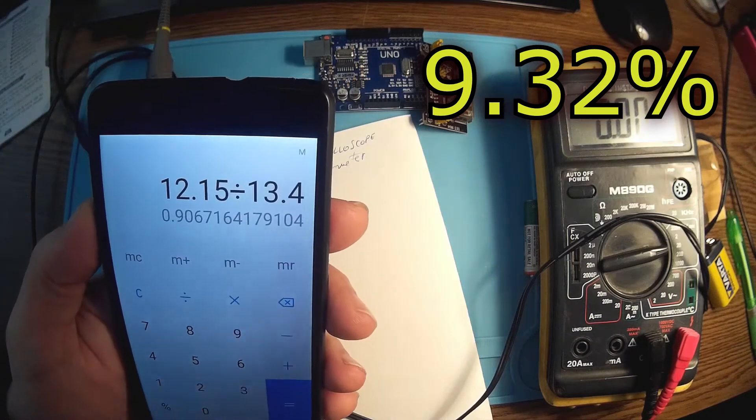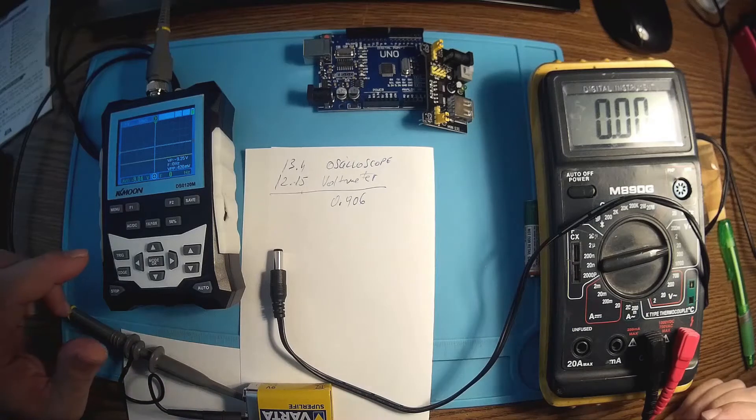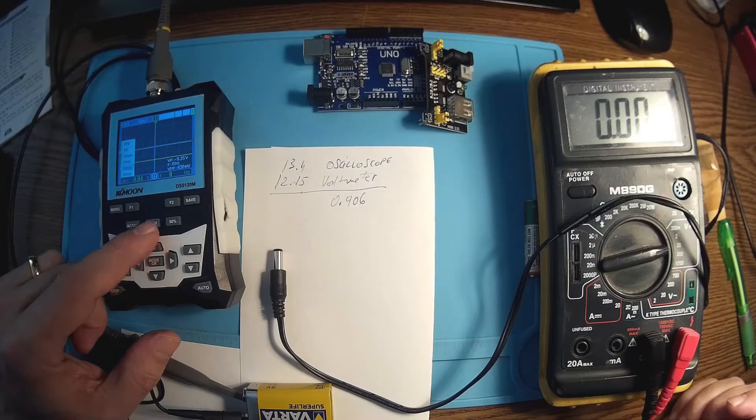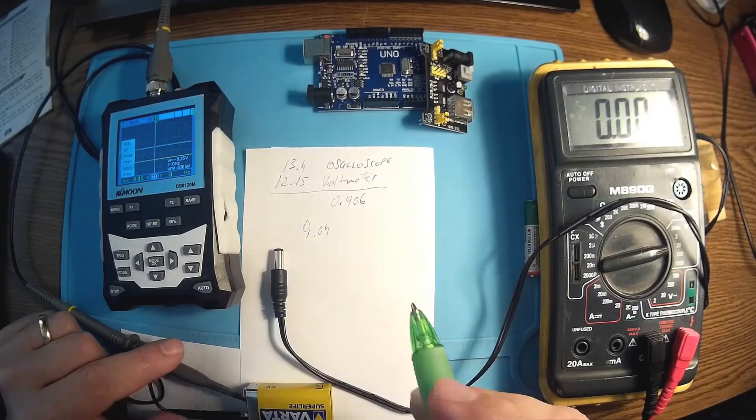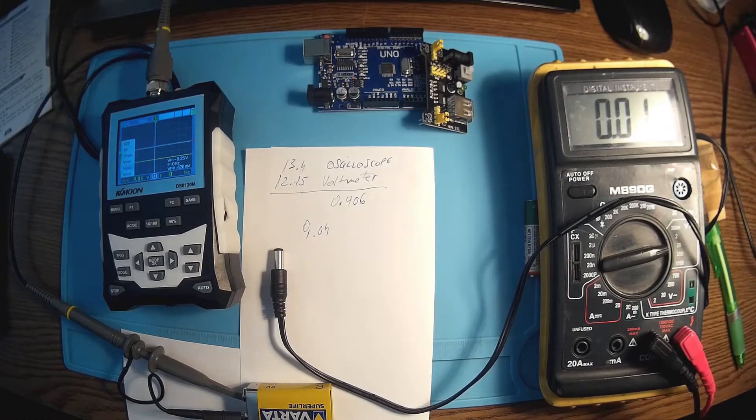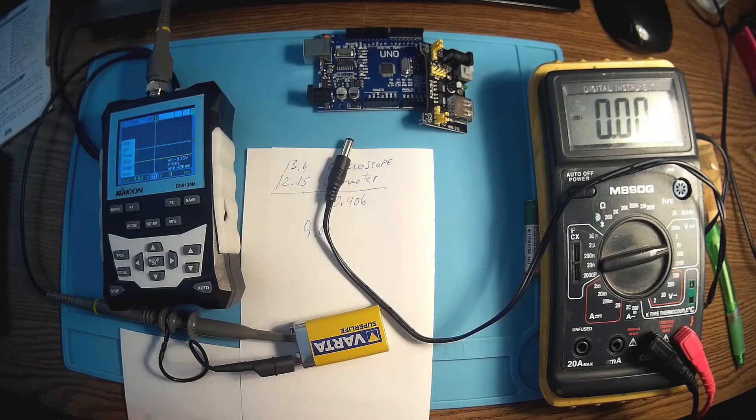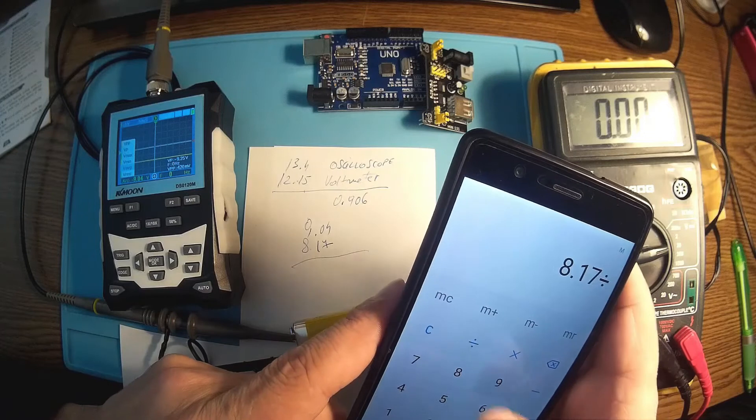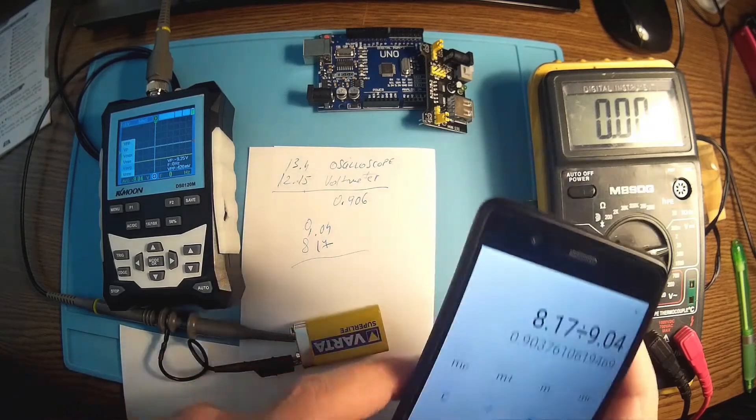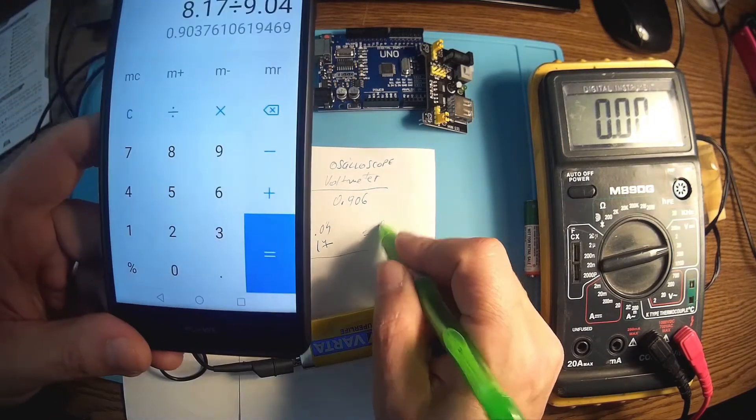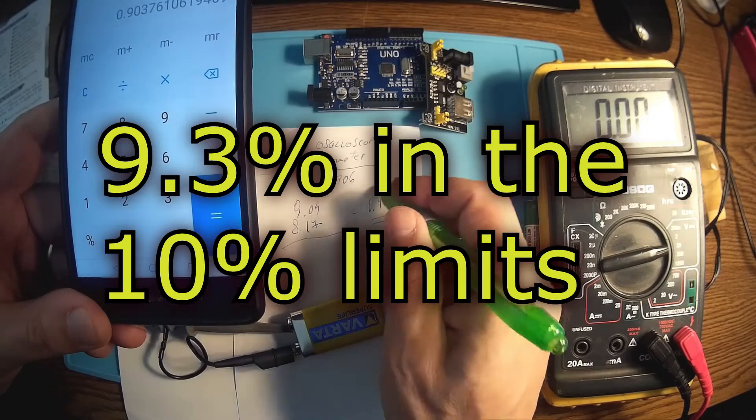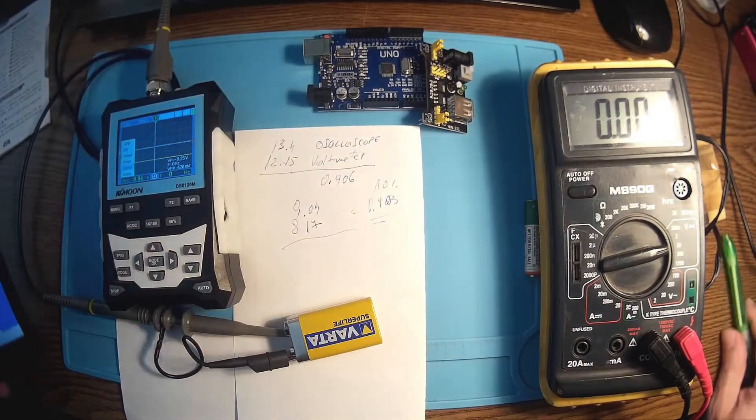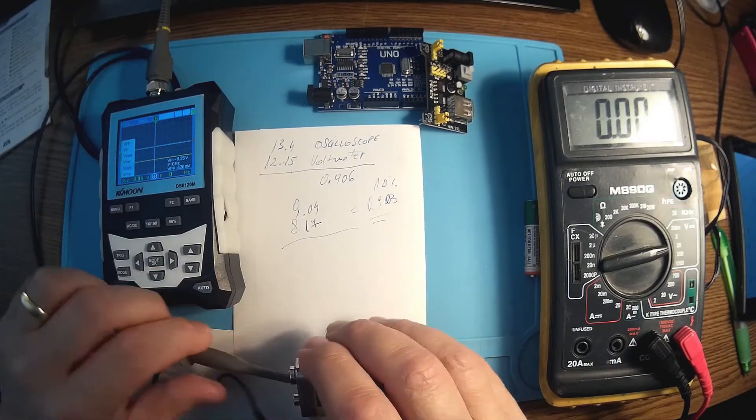Now I changed the polarity here and we have average of 9.04. And let me see the voltmeter again, 8.17. 8.17 divided by 9.04, so we almost have the same numbers, equals 0.903. It's in the 10% limit, no doubt about it. This is about batteries.